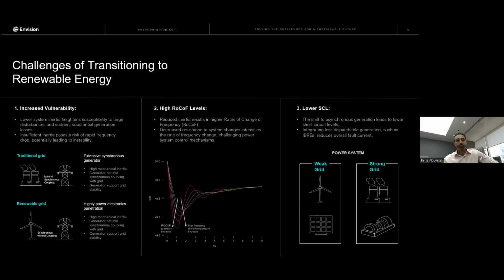Another section is the high rate of change of frequency, which we call ROCOF, and the high rate of frequency levels challenges the power system control, causing instability and not being able to manage properly. Finally, we have the SCL or SCR, depending how you look at it, which is shifting towards renewable energy, leading to low short circuit levels. This means fewer fault current systems, making it harder to maintain stable voltage and frequency in island grids.